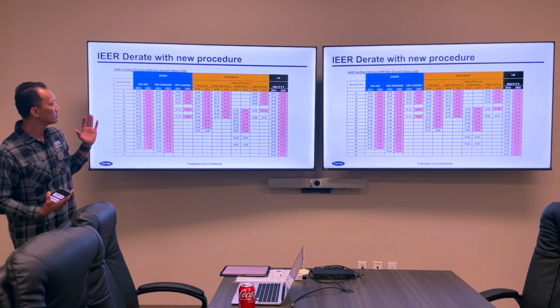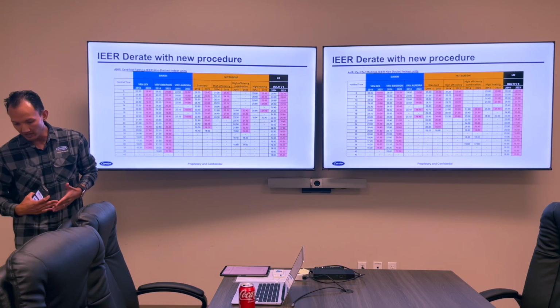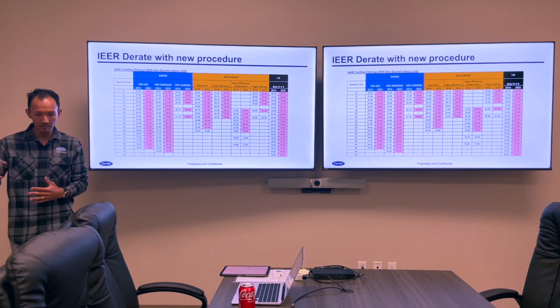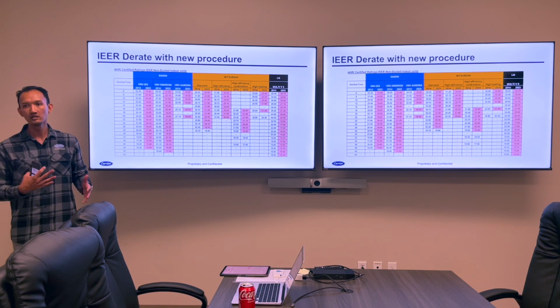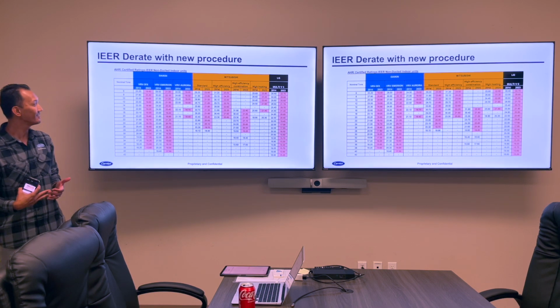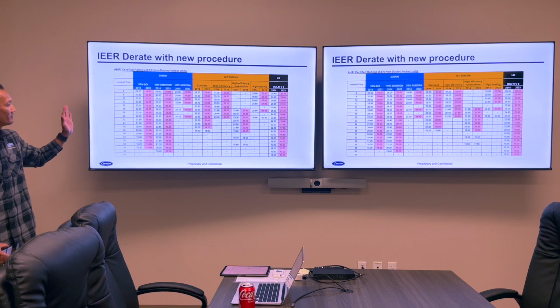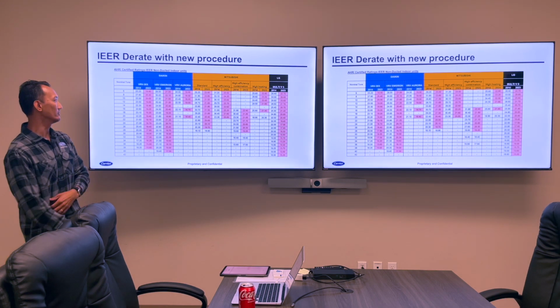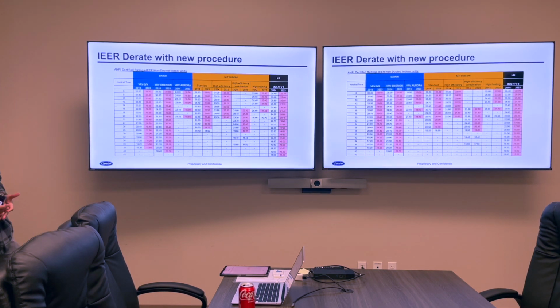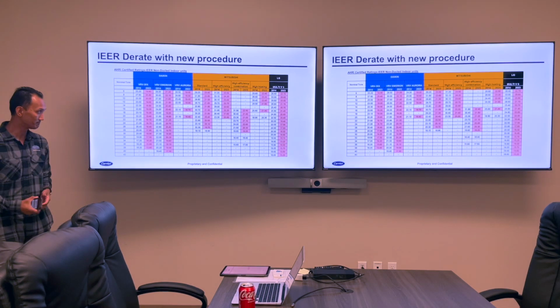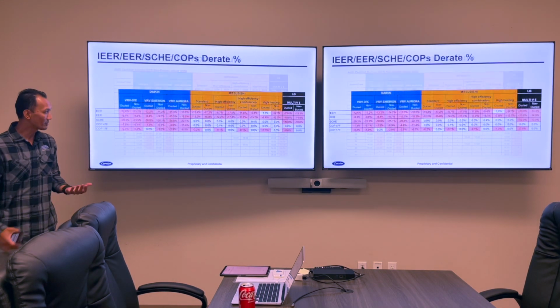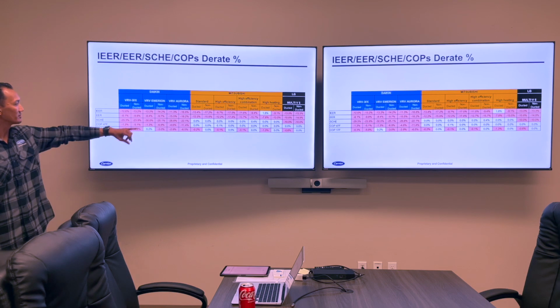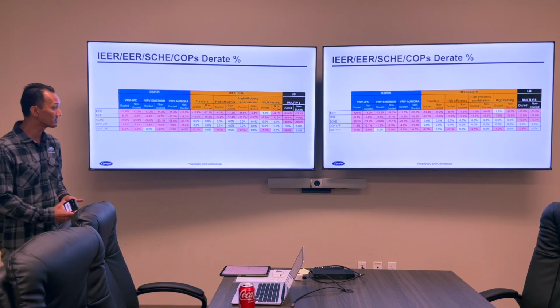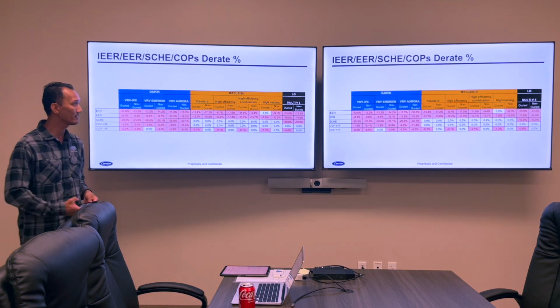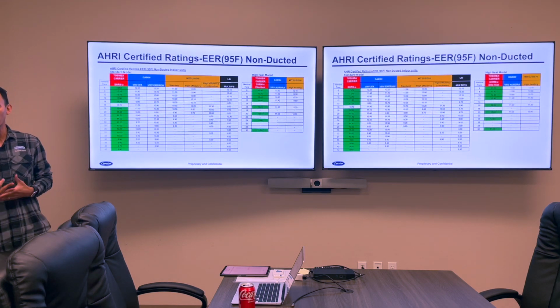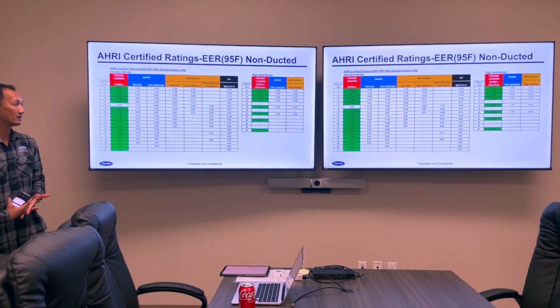And what we did was we took some of the efficiency ratings from the previous method and compared it to the new method. And you'll notice some pretty interesting things that happened as far as the efficiency ratings. A lot of them went down when you compare the previous method to the current method. If you look at it as a percentage, some of the percentages show as much as a 30% efficiency drop with the new testing method. And then if you add in our Toshiba Carrier line, how it looks compared to the rest.